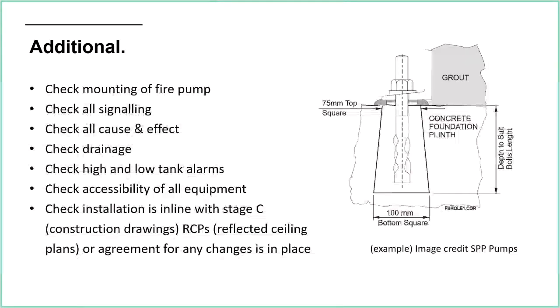A colleague of mine mentioned to me about these ChemFix bolts. There are two different types of fixings. I forget what the other one's called, but that's an example there of the standard bolt fixing. But this ChemFix system involves an epoxy resin filling, and that takes 72 hours to cure. So again, if commissioning is in a bit of a rush, what we don't want to happen is for them to quickly fix the pump down using the ChemFix and then run the pump, because you're going to get problems there.